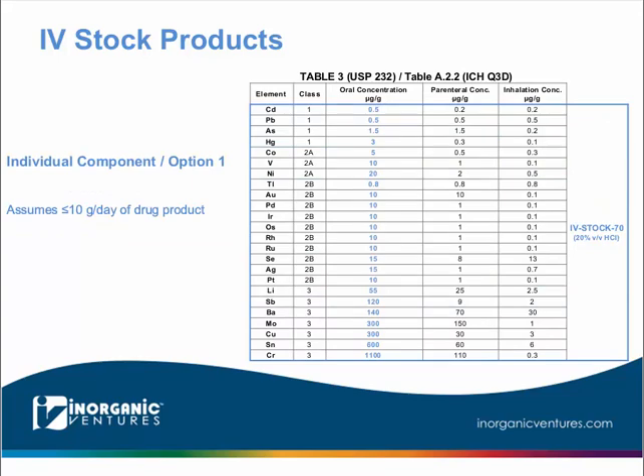The sixth product we are offering for 2018 is based upon the limits described in table three of USP 232, which corresponds to table A22 in Q3D. This data table represents the individual component approach described in 232, also known as option 1 in the Q3D method. This particular product, IV stock 70, represents a combination of all 24 of the elements specified in the methods, which is possible due to the lower concentrations detailed for the class 3 elements. This is the only product we're currently offering as a stock that's not directly based upon the permissible daily exposure table, and it primarily reflects the number of unique requests we've observed.